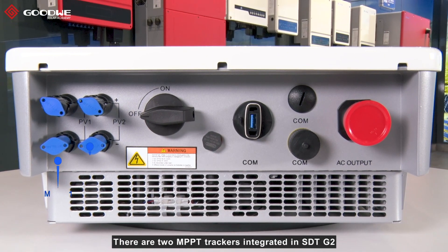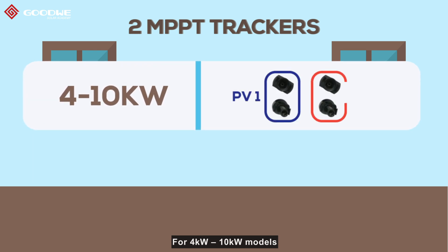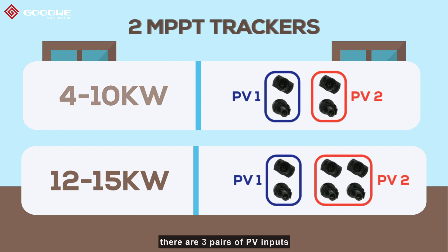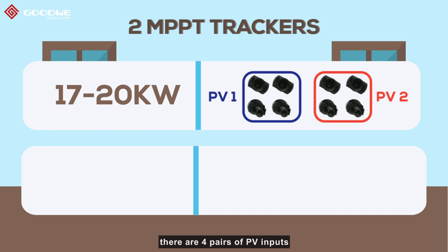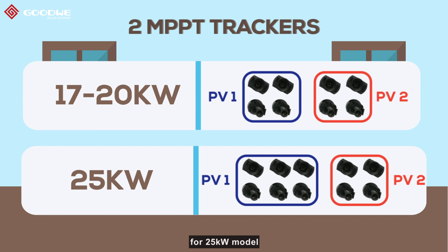There are two MPP trackers integrated in SDT-G2. For the 4kW to 10kW models, there are two pairs of PV inputs. For the 12kW to 15kW models, there are three pairs of PV inputs. For the 17kW to 20kW models, there are four pairs of PV inputs. For the 25kW model, there are five pairs of PV inputs.